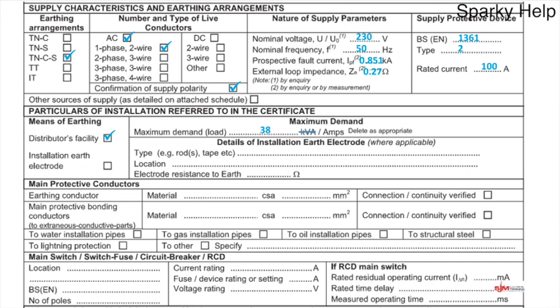So we're going to go for 38 amps. You're not supposed to be putting in 100 here, because if you put 100 in here, you're saying the maximum demand of the entire installation is 100 amps. If I was to come back in a couple of years' time and they said they would like to put an electric vehicle charger in, I'm going to ask for the previous test sheet, and I will see that you said it's 100 amp as a maximum demand, and I'm about to add another 32 amp supply to it.